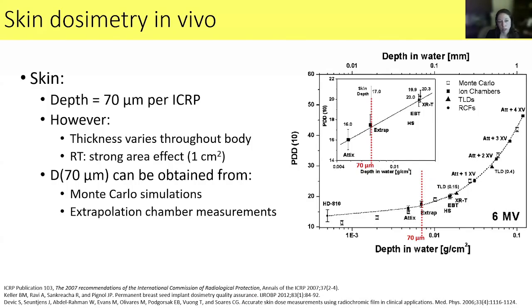So anyway, if you were interested in getting dose at 70 microns depth, then you can get this from Monte Carlo simulations or extrapolation chamber measurements. And then those results can be used to determine correction factors for other detectors that can be used in vivo that have differing water equivalent depths.